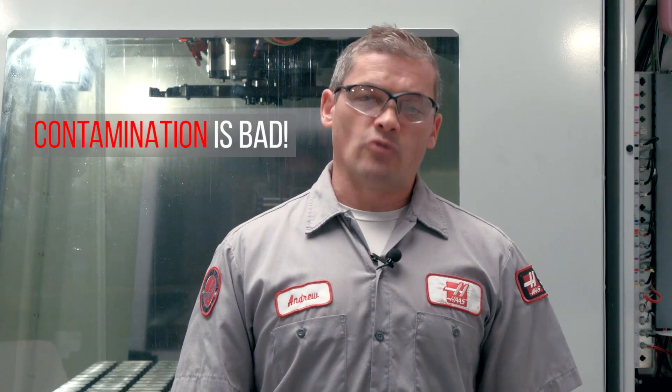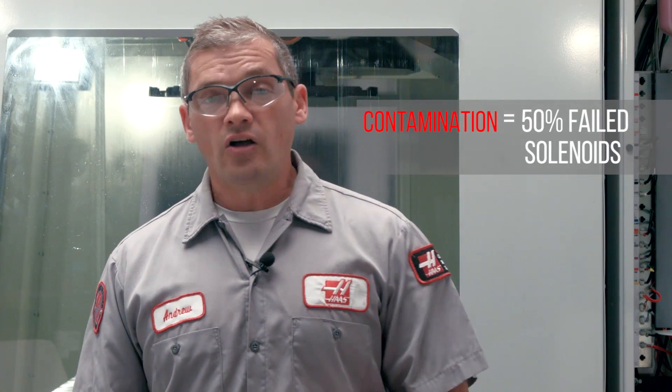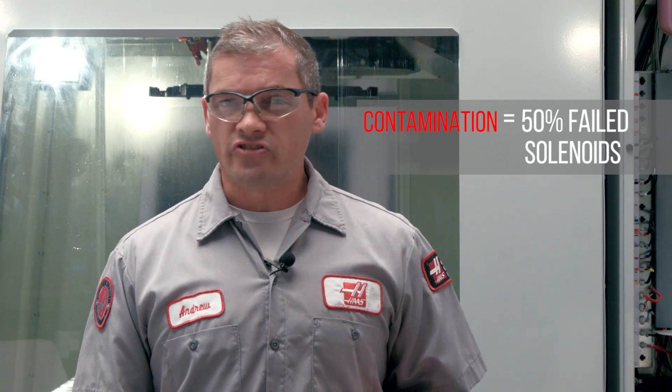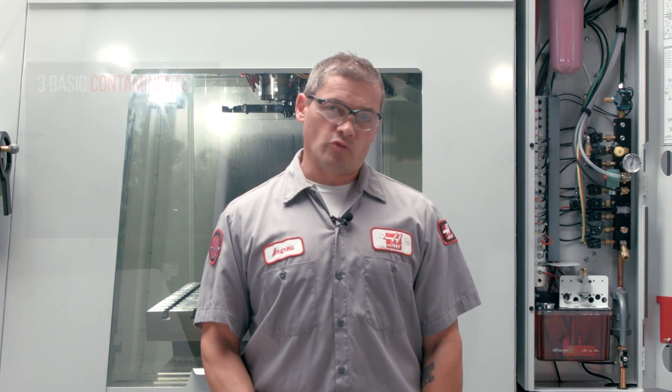But before we get started with that we're going to stop and take a detour to discuss what's maybe the most important part of this video. And what's that you might ask? Contamination is what we're talking about. Based on returned solenoids that Haas receives, at least 50% of all solenoid failures are due to some form of contaminated air. And there are three basic contaminants we're talking about here: oil, water, and particulate.